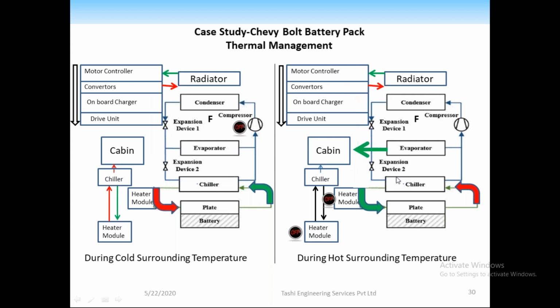The procedure we follow is to select a value that mostly overlaps with our operational zone, say 2000 watts. But we do ensure that the brief period—say 7 to 10 seconds—where the heat load reaches 6000 watts is included in our design. So when the heat load for those 10 seconds becomes 6000 watts, I can control my compressor to run at higher RPM for that duration, so that design point is included within my thermal management system.